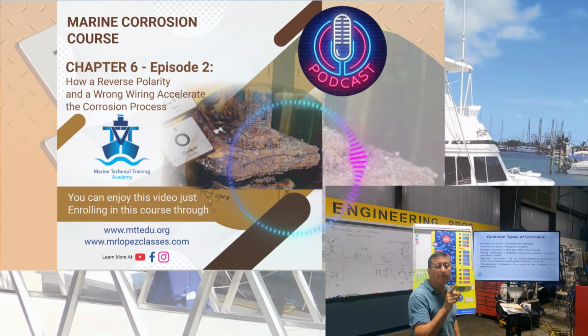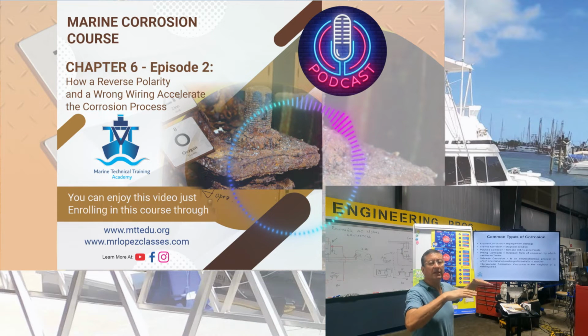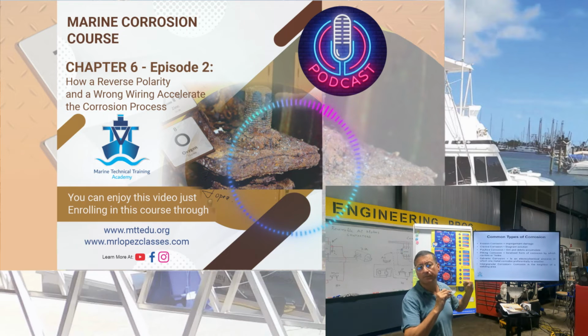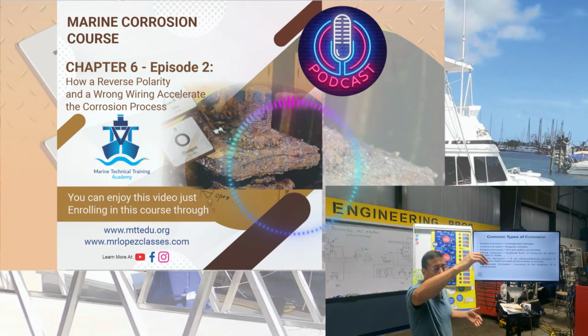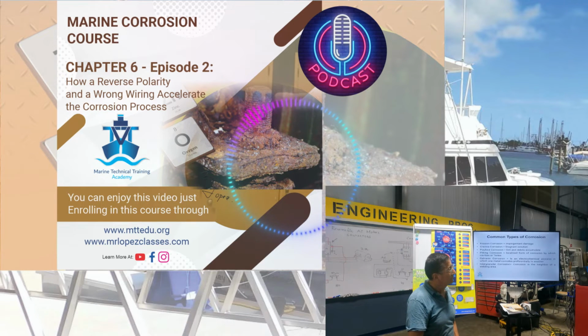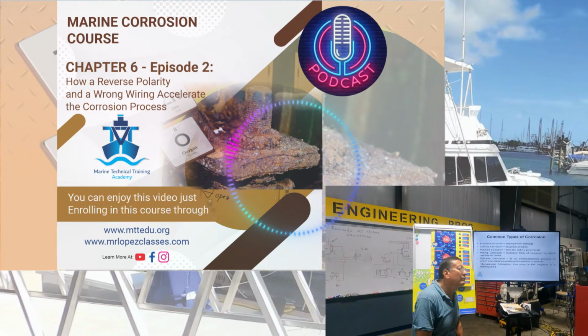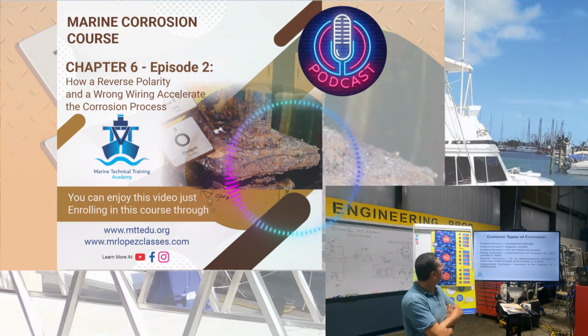Some technicians, some captains, instead of a switch selector with three positions, prefer three individual breakers with a slide bar. They say, oh, I am going to use my boat right now on shore power. I turn this one on and the other ones off, inverter and generator. No, I want to work right now with the inverter. Okay, inverter on, off and off. No, I want to select generator right now. Okay, generator on, off and off. Some people prefer the independent breakers, or the switch selector. The switch selector is too expensive in comparison with this.